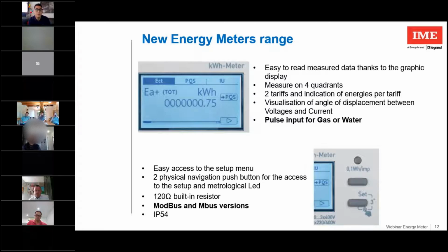In the part below, a focus of the new and more user-friendly buttons. With the long press of the set button, you can enter into the setup and view all the parameters. If you want to change these parameters, you have to input a password. Default is 1000, but you can put a custom one. So if an electrician doesn't know the password of this energy meter, but only wants to know, for example, the Modbus address, you can check it without changing anything. So you can enter into the view of the configuration and not change anything.